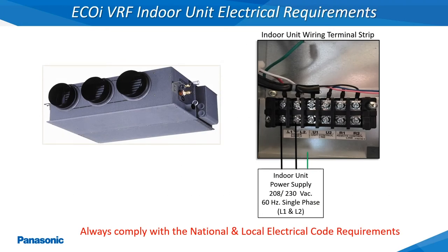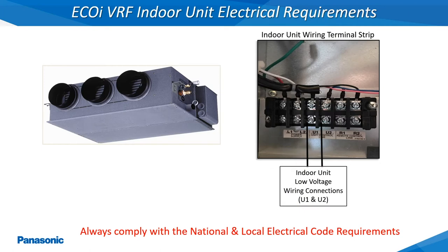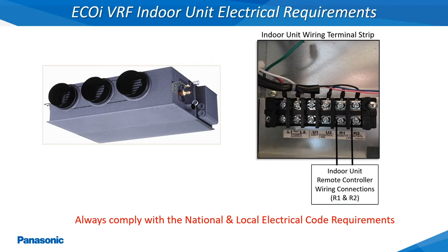All of the ECOi indoor units will require a 208 or 230 volt, 60 hertz, single phase power supply connected to the L1 and L2 terminals of the indoor unit along with the ground wire. The low voltage communications wiring installed from the outdoor unit will be connected at the U1 and U2 terminals of all the connected indoor units and must be installed using an 18 gauge 2 conductor stranded and shielded wire. The remote controller wiring is connected to the R1 and R2 terminals of the indoor unit as an 18 gauge 2 conductor stranded and shielded wire.